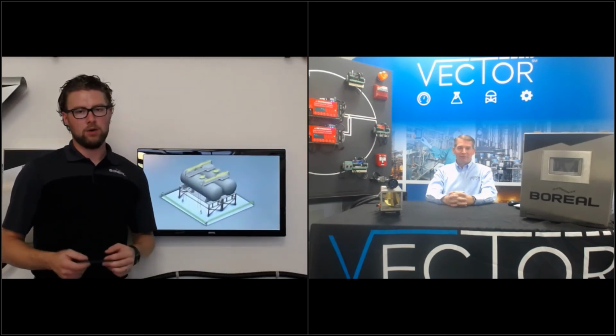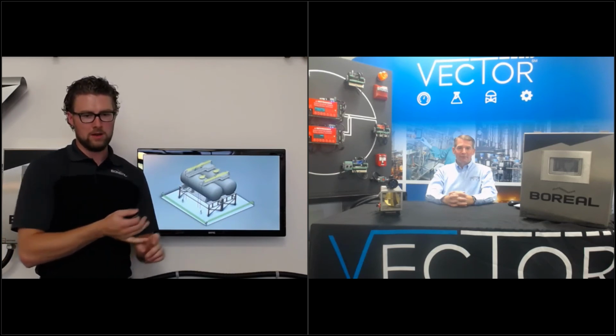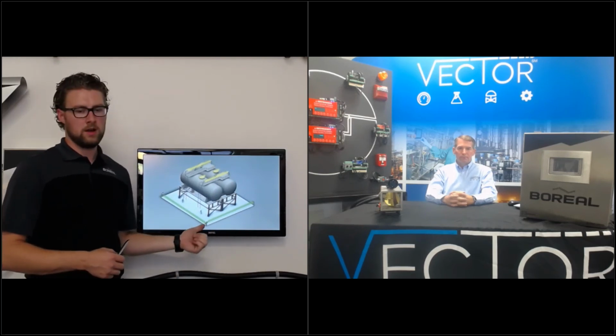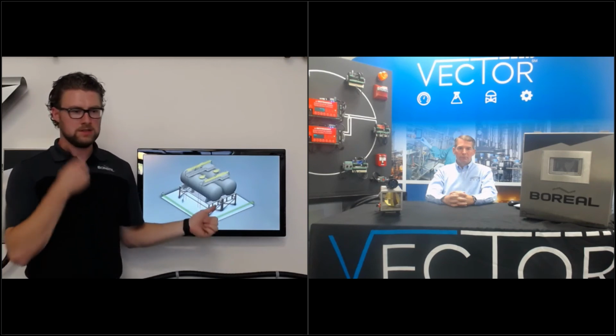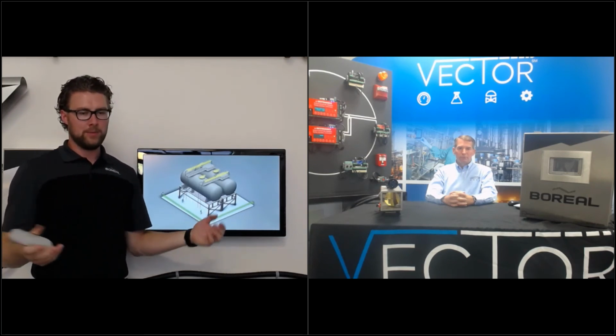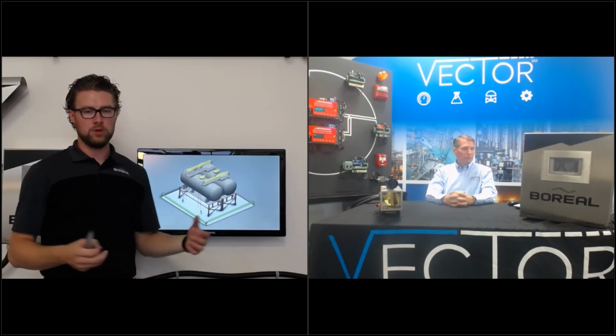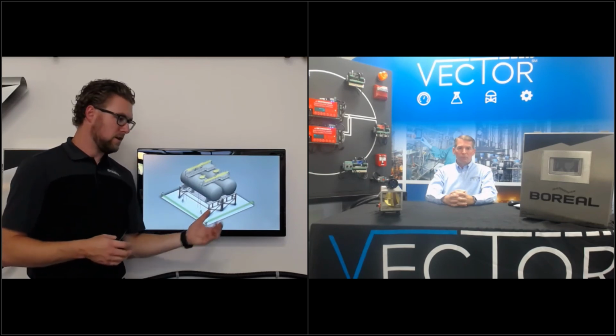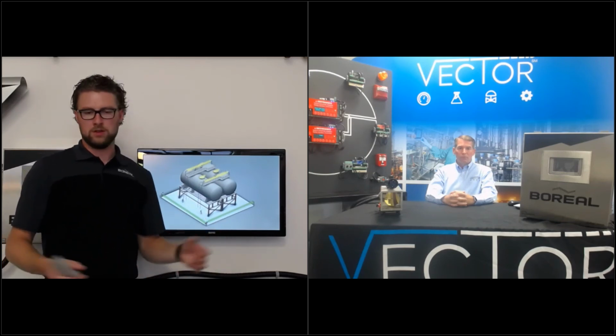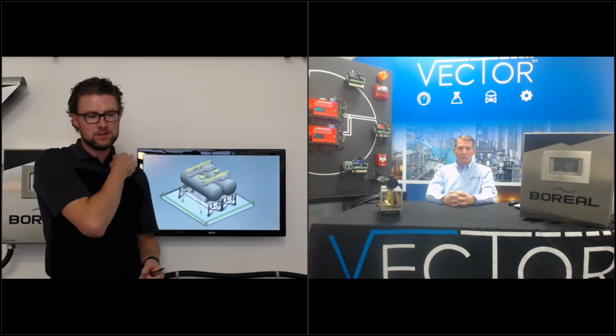Excellent. So within the power industry, whether it's coal-fired power generation or anything in relation to the reduction of NOx emissions, so selective catalytic reduction applications, the use of anhydrous ammonia as a scrubbing agent in SCR applications, we can measure for leaks at storage bullets and tanks. In power applications, we can monitor for ammonia leaks in and around the vaporizer or the Diva skid applications as well. And certain other industries, if you're interested in fertilizer or anything else like that, there are numerous.